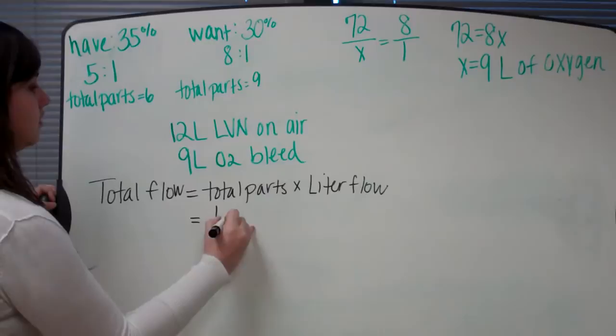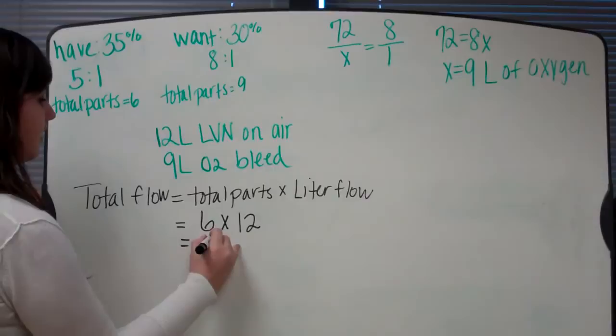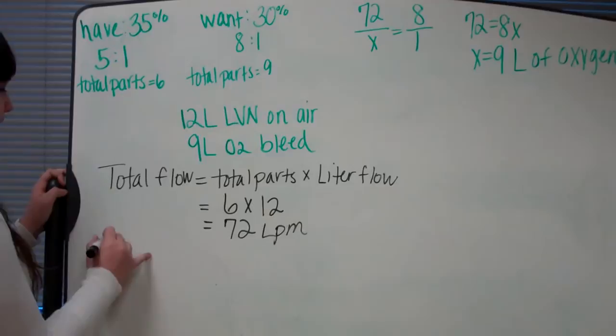So 6 times 12 liters, which is what the 35% is on, equals 72. So our 72 is our total flow, liters per minute, for our 12 liter LVN on air.